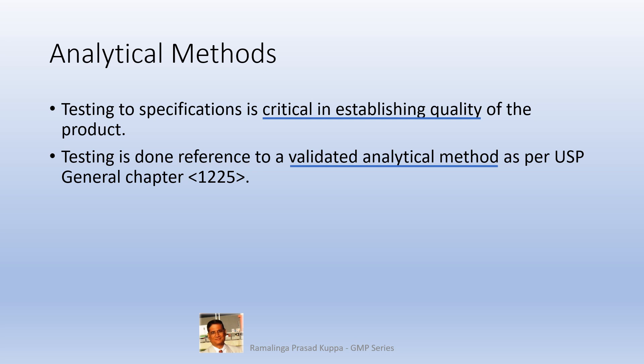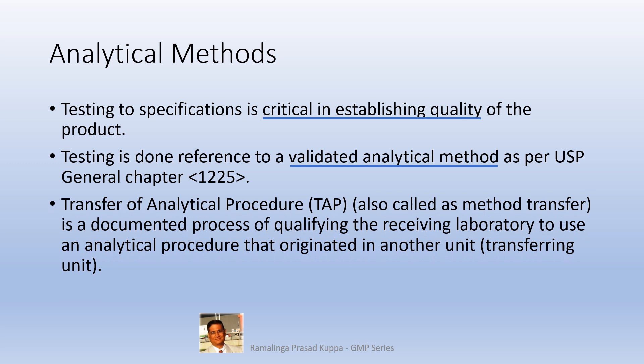Typical characteristics described in USP 1225 are precision, accuracy, specificity, detection limit, quantitation limit, linearity, range, and robustness. These are important items required for method validation, and all such methods must be validated before being put into routine release testing. Transfer of analytical procedures, also called method transfer, is a documented process of qualifying the receiving laboratory to use the analytical procedure that originated in the transferring unit. Transfer is done for a validated test method only.